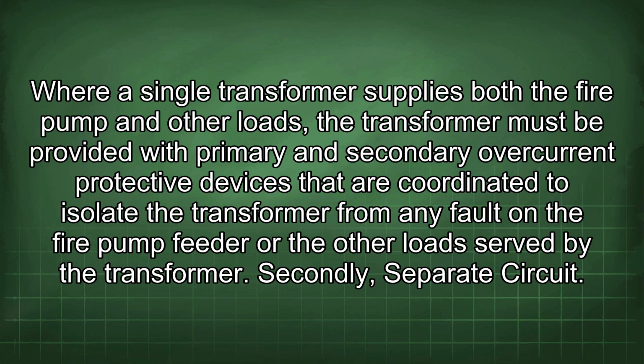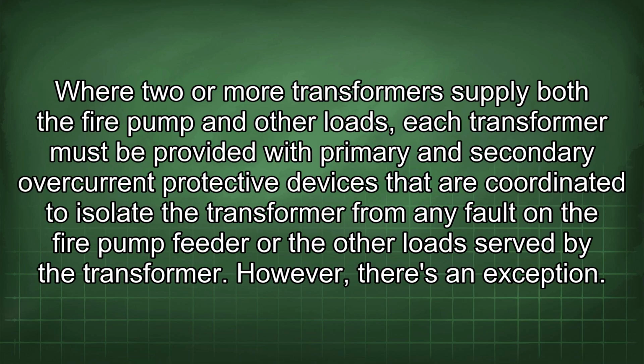Secondly, separate circuit. Where two or more transformers supply both the fire pump and other loads, each transformer must be provided with primary and secondary overcurrent protective devices that are coordinated to isolate the transformer from any fault on the fire pump feeder or the other loads served by the transformer.